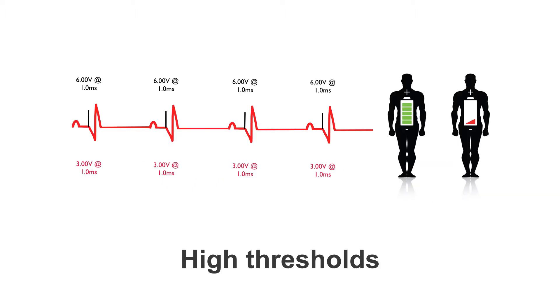What do I mean by this? If we have higher thresholds — something like 3 volts at 1 millisecond — to be safe, we would set the pacemaker output pulse to 6 volts at 1 millisecond. We can see that the pacemaker will still perform appropriately. However, using this much energy every time you need to trigger a depolarization will be a huge strain on the battery. Ultimately their device will not last as long, and in their lifetime they will end up having more surgeries to replace their pacemaker.